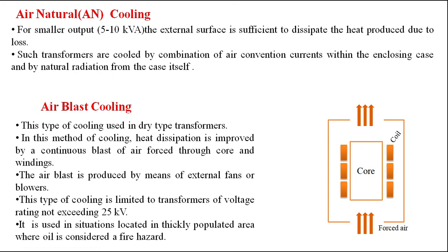For the dry type of transformer, that is smaller capacity transformer, we are adopting two methods. For air natural cooling, in the range of 5 to 10 kVA, the external surface is sufficient to dissipate the heat. You simply keep the transformer wherever it is being used, and the natural air around the transformer is sufficient for cooling. Such transformers are cooled by a combination of air convection currents within the enclosing case and by natural radiation from the case itself.